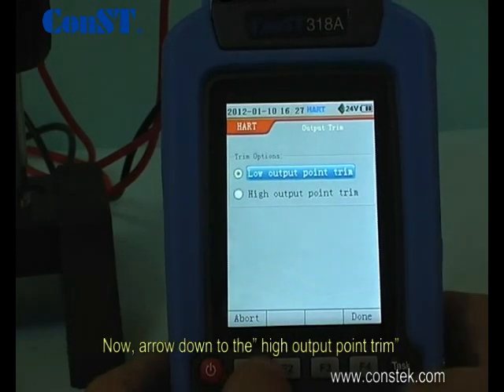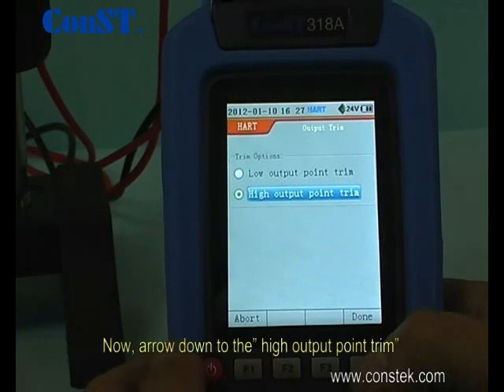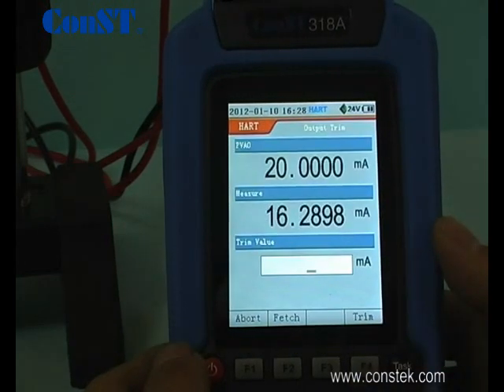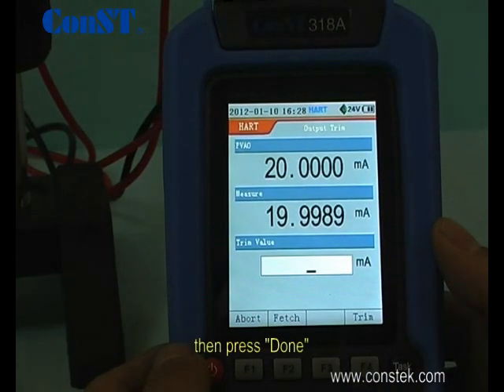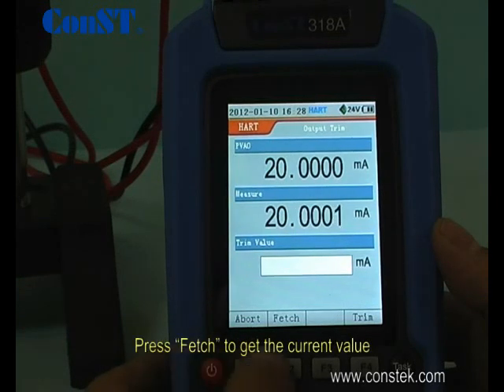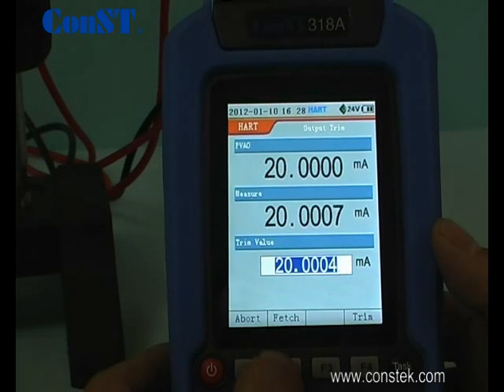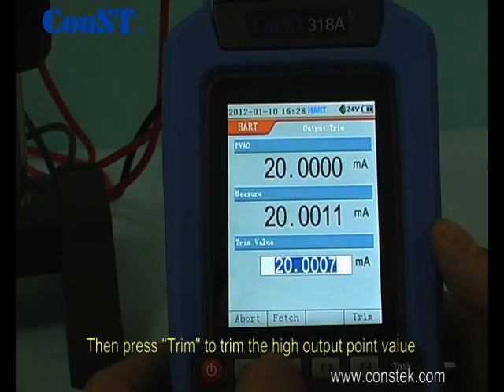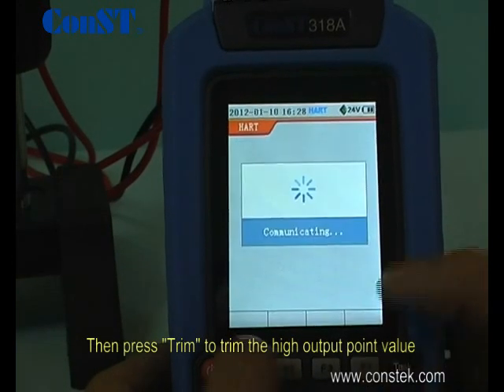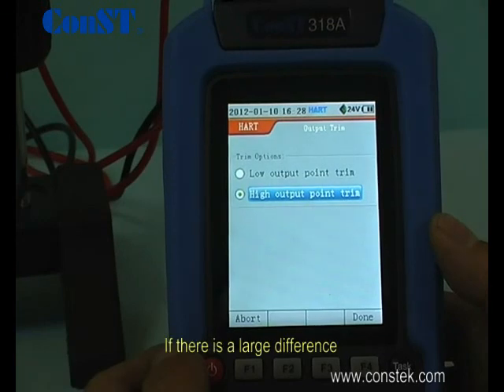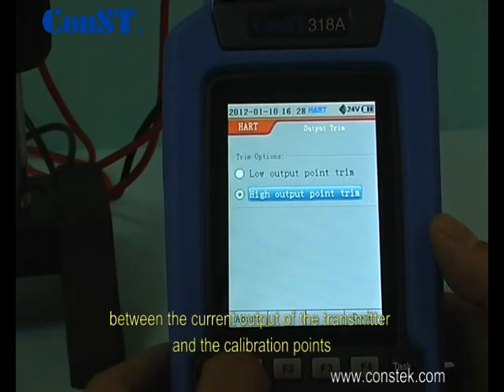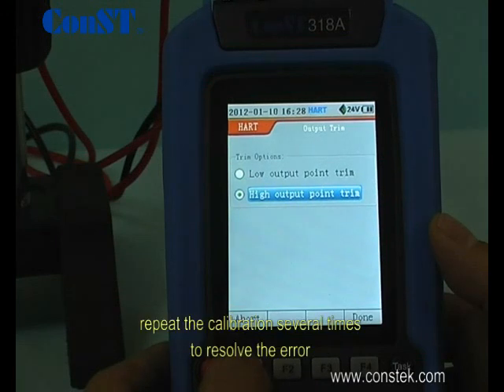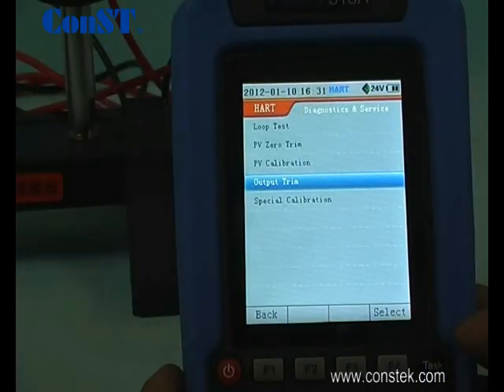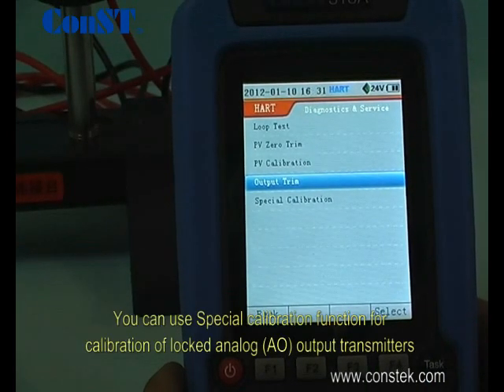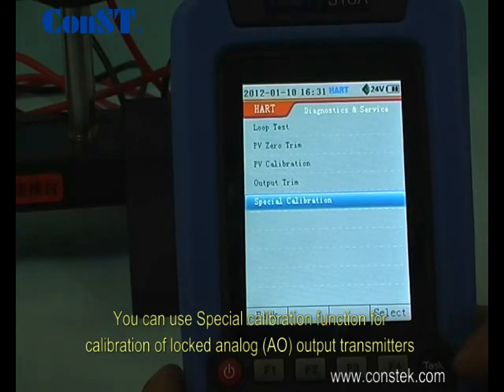Now arrow down to the high output point trim. Then press Done. Press Fetch to get the current value. Then press Trim to trim the high output point value. If there is a large difference between the current output of the transmitter and the calibration points, repeat the calibration several times to resolve the error. You can use the special calibration function for calibration of locked analog output transmitters.